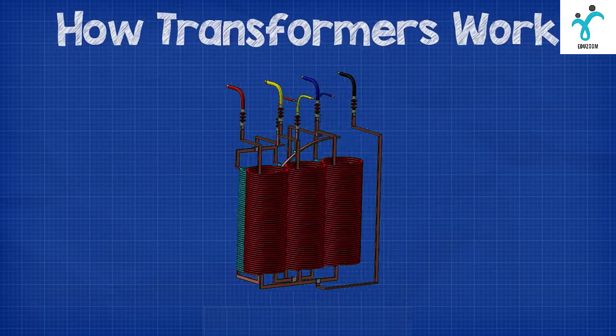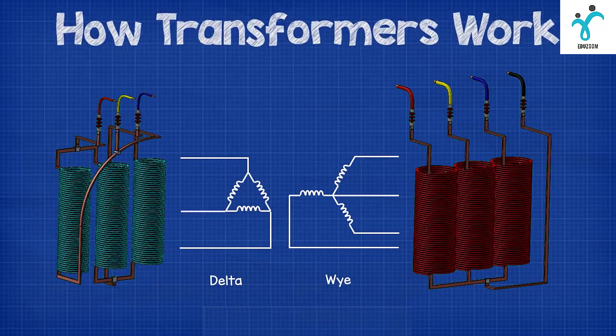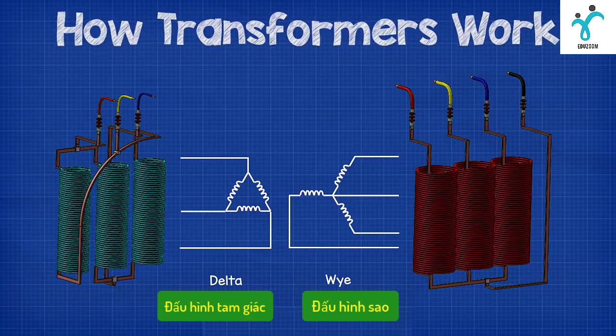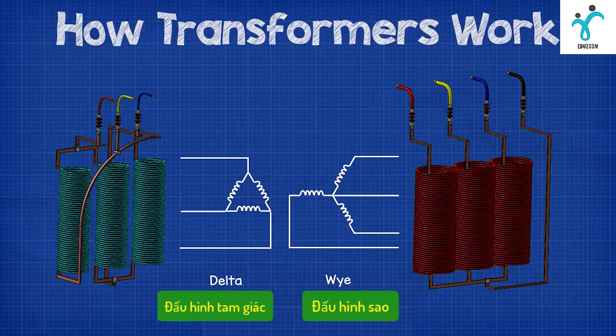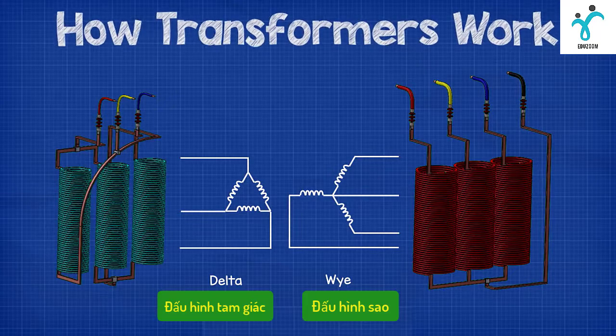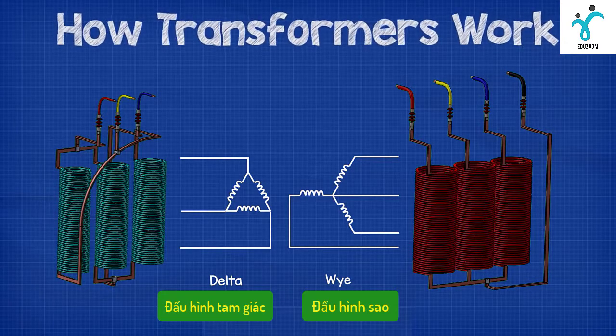To connect the two sides there are many different configurations, but one of the most commonly used is to connect the coils in a configuration known as Delta Y, sometimes referred to as Delta Star. This refers to the primary side being wired in a Delta configuration and the secondary side being wired in a Y configuration. The center point of the Y side where all three connectors meet is often grounded, which allows for a neutral line to also be connected. We'll cover transformer connections and calculations in other more advanced videos, so for now simply focus on how they work to build your base knowledge.